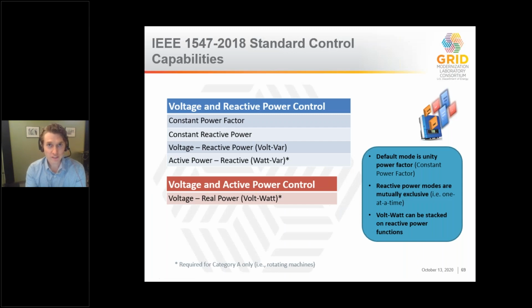Moving into the standard control capabilities that will help facilitate DER integration, by standard I mean these are based on the IEEE 1547 2018 revision, which is going to result in equipment availability, most expect sometime around the beginning of 2022. There are 5 different functions, all relying on those 2 basic mechanisms discussed earlier: controlling active power or adjusting reactive power.